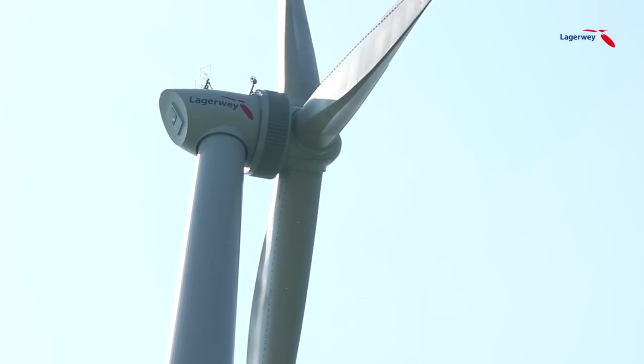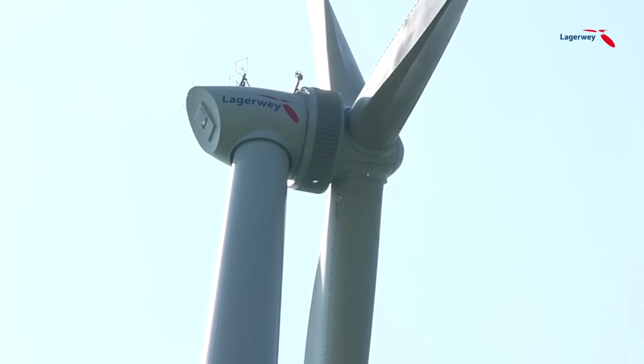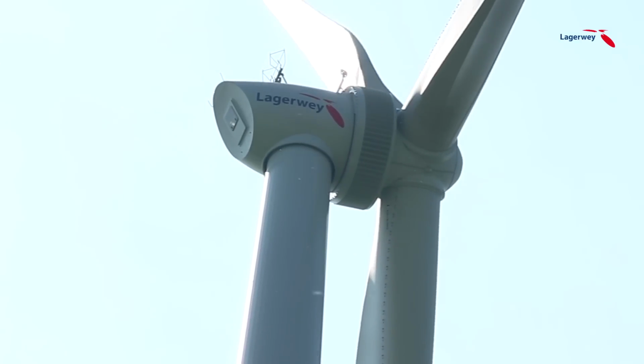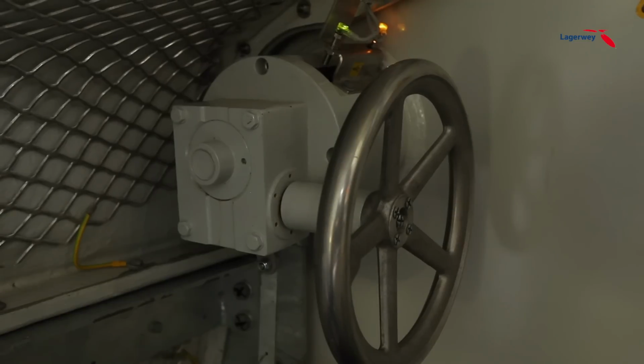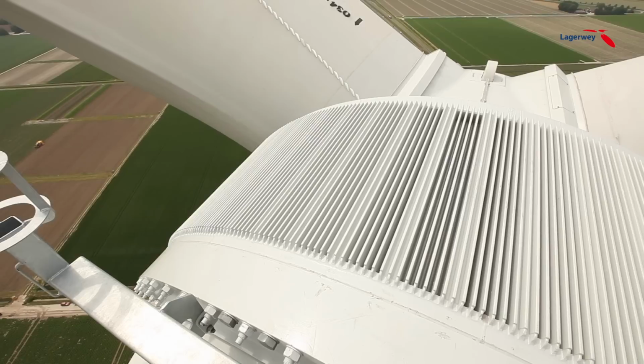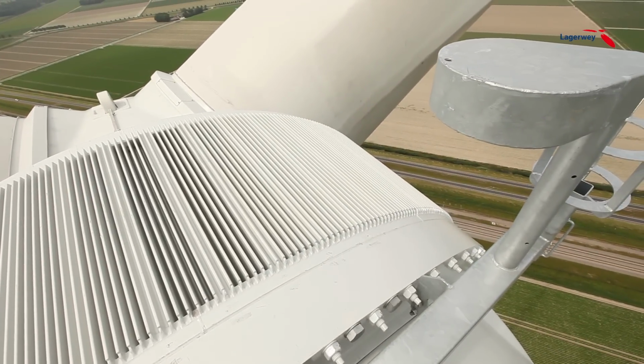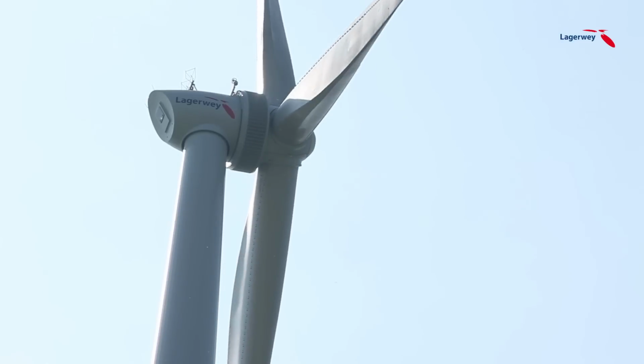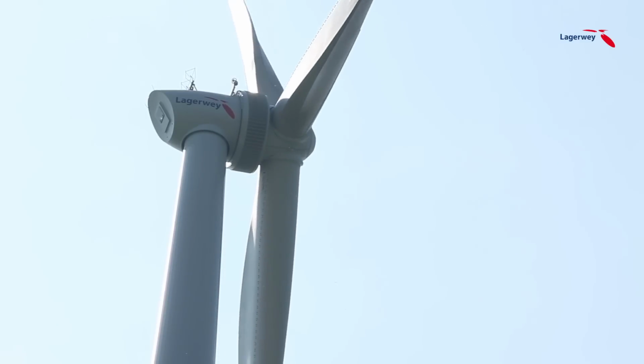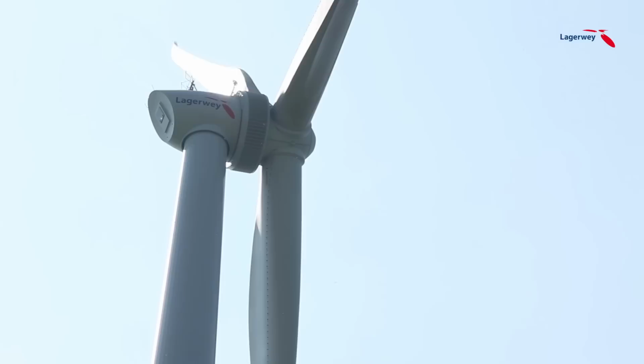The most important component of the turbine is held by the main bearing, the generator. The rotor is directly mounted onto the generator, automatically synchronizing the speed of both devices. The generator is completely sealed from its environment. This makes it withstand extreme conditions. And thanks to the lack of a gearbox and accompanying oil lubrication system, this generator easily handles very cold weather conditions. The relatively small energy losses, which is made possible through its very efficient design, are converted into heat. This heat is efficiently dissipated to the outside air through the cooling fins around the perimeter of the generator.